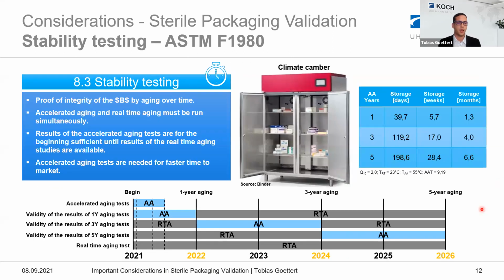So beside the performance testing, now we are at the stability testing. This is to prove that your sterile barrier system can still maintain the sterility after aging. Therefore, you have two options. You can do accelerated aging with a climate chamber or environmental chamber, and real-time aging. The standard says you have to do both. You can use the results from accelerated aging to speed up your time to market, but you have to do real-time aging at the same time.